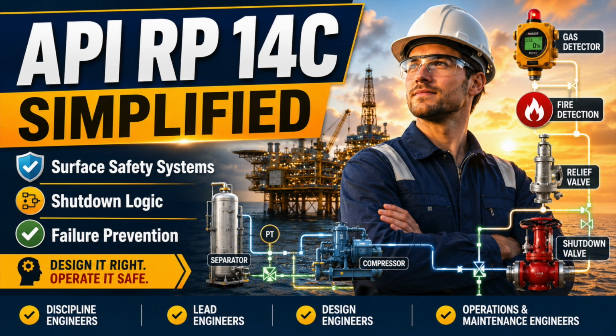A temperature controller regulates heat input, but a high-temperature shutdown exists because fuel systems, heat sources, and control logic can fail. The process control system keeps the plant running. The safety system stops the plant from becoming dangerous when control fails. Do not blur those roles.